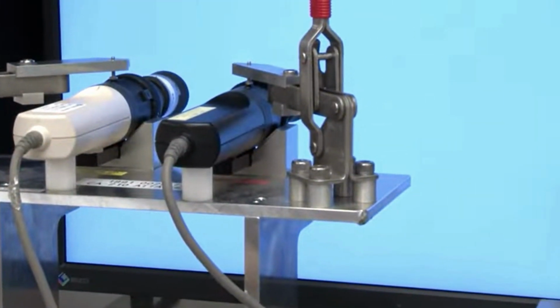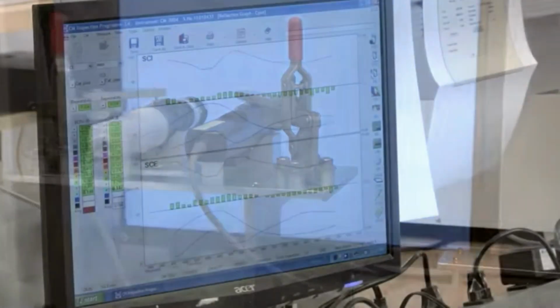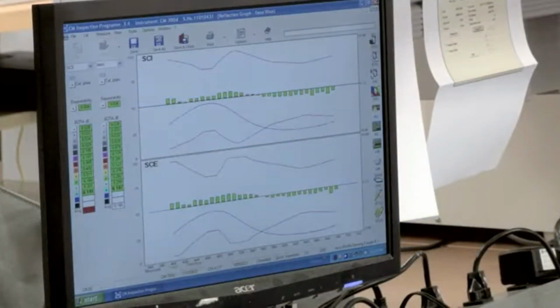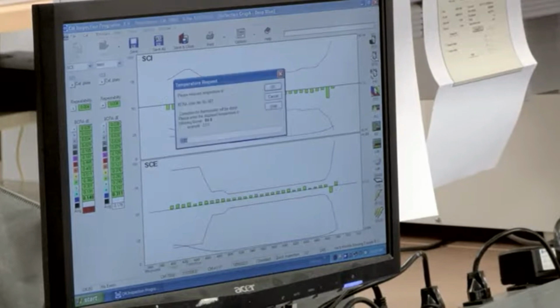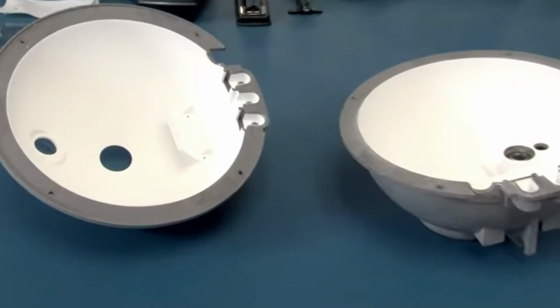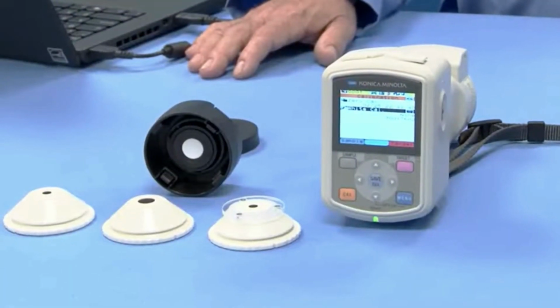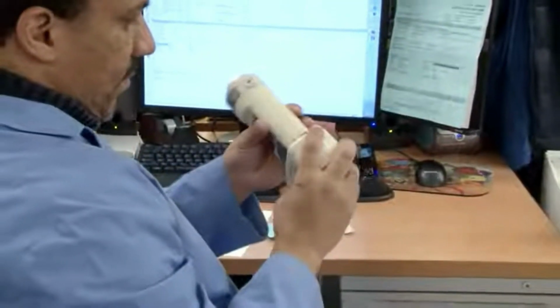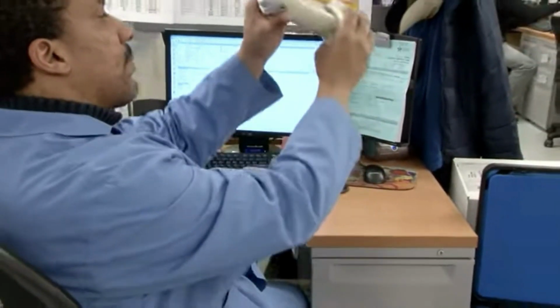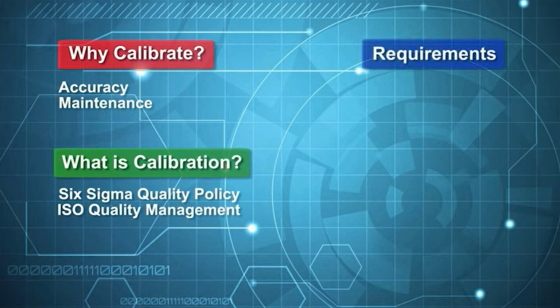We get the question quite a bit from customers, why should I calibrate my equipment? And the reason is that over time, instruments will drift, optics will get dirty, and these things need to be cleaned and brought back to factory conditions. And the instrument needs to be functioning perfectly as opposed to over time drifting. To maintain your Konica Minolta sensing instrument, daily calibration is necessary. In addition, annual yearly calibration maintains the accuracy of your instrument over time.